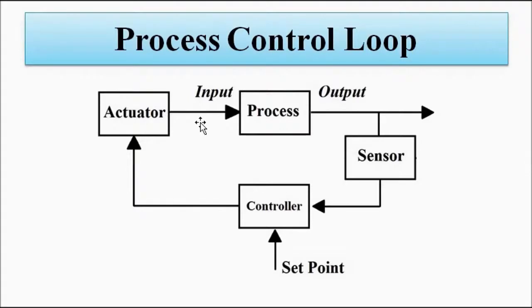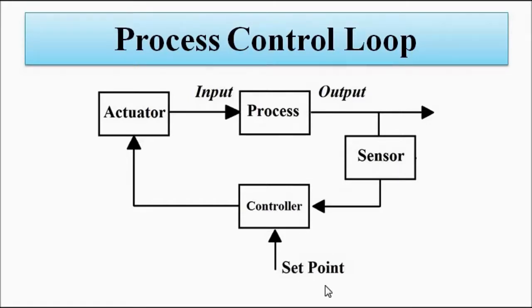A basic process control loop operates with the process having an input and an output — that is a simple open-loop process. When a feedback path is involved, various other components come into play, such as a sensor or transducer that measures the output and gives that reading to the controller, where it is compared with the set point value — the desired output value. The controller then calculates the error signal, the gap between the actual and desired output, and takes suitable control action via the actuator to manipulate the input to the process.